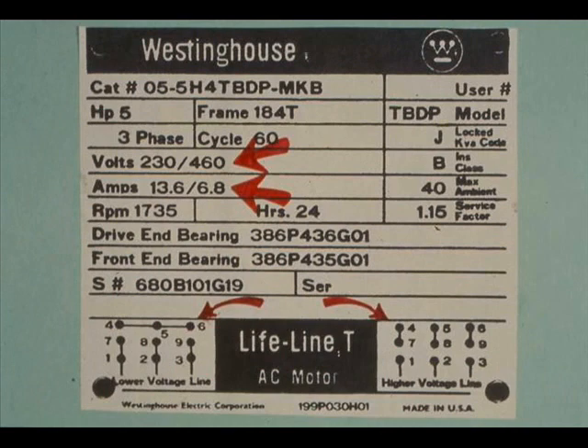The rated volts and full-load amperes must also be stated. This motor may be wired to operate at either 230 or 460 volts. Note the wiring diagrams included for the electrician's guidance. At 230 volts, this motor draws 13.6 amperes. At 460 volts, it draws 6.8 amperes.